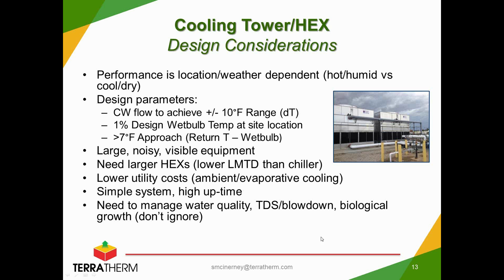They tend to be loud, noisy equipment, and because you're at the mercy of Mother Nature and potentially have higher temperatures of the cooling water loop, based on a cooling demand that often translates to needing larger heat exchangers to get the amount of cooling you need for the project. The benefit of these is that, again, you're dealing with evaporative cooling and ambient temperatures to provide the cooling effect we're looking for. And so they can be low utility cost type cooling applications.